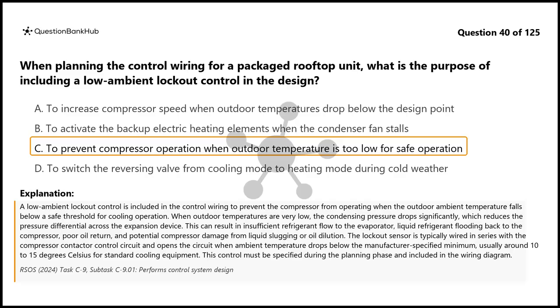The lockout sensor is typically wired in series with the compressor contactor control circuit and opens the circuit when ambient temperature drops below the manufacturer-specified minimum, usually around 10 to 15 degrees Celsius for standard cooling equipment. This control must be specified during the planning phase and included in the wiring diagram.